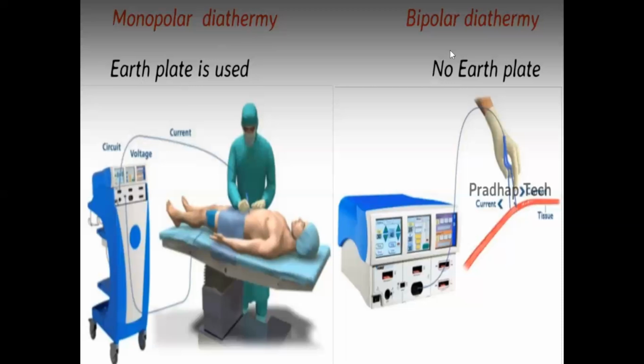Bipolar diathermy, no earth plate. The current that comes from here goes to one pole, and the energy that transmits between the poles goes back via the cable to the machine itself. It doesn't pass through the patient's body. That's why bipolar is safe. There is no current transmission via the patient's body. It doesn't use our body as a passage. That's why bipolar is safe.